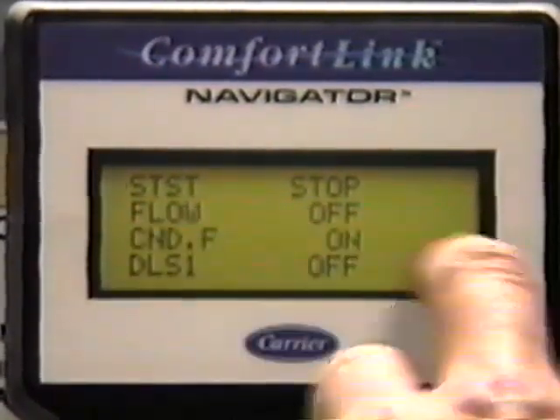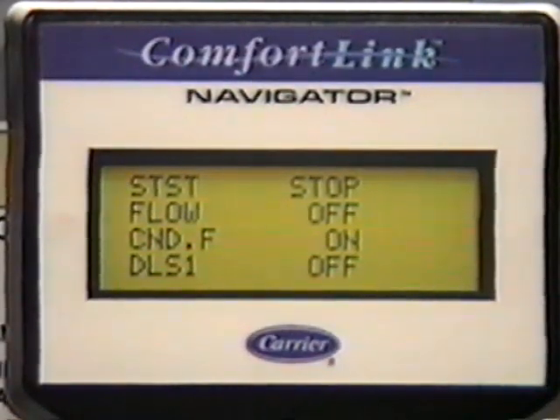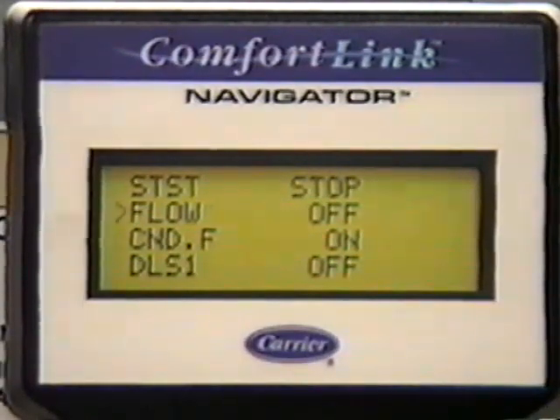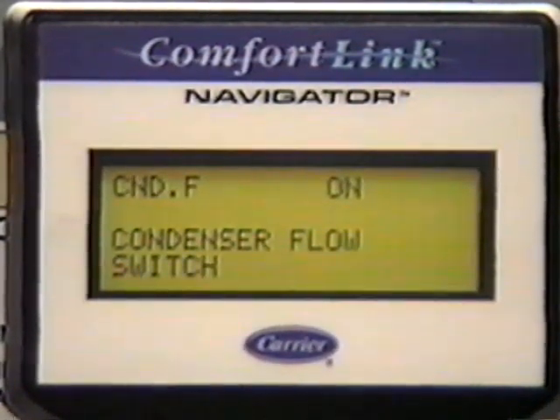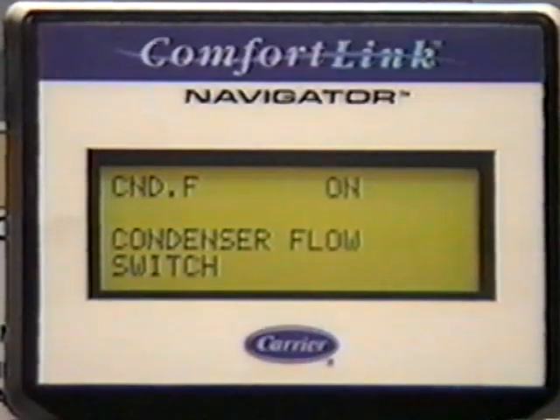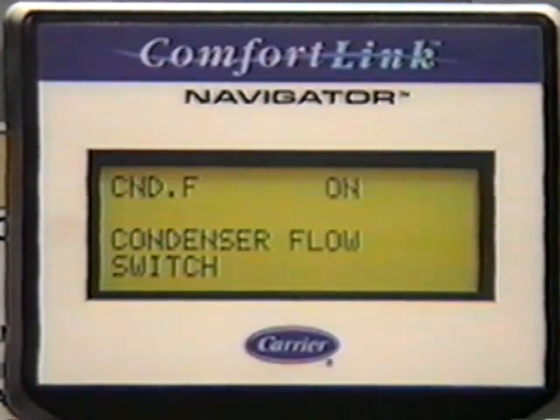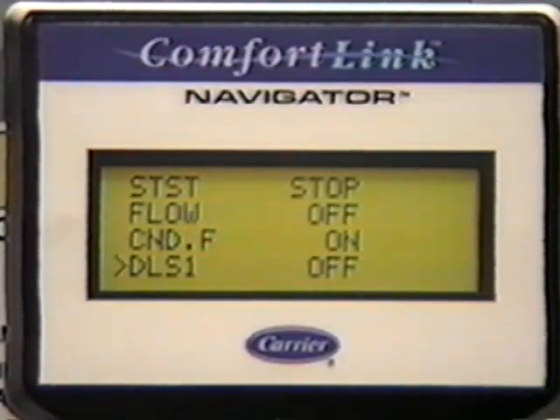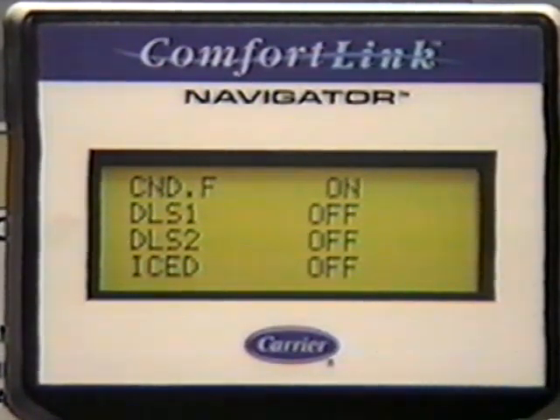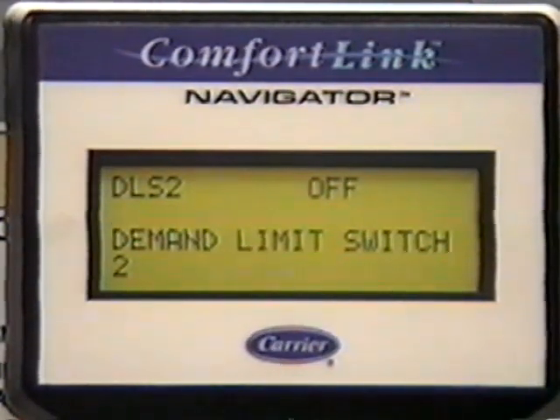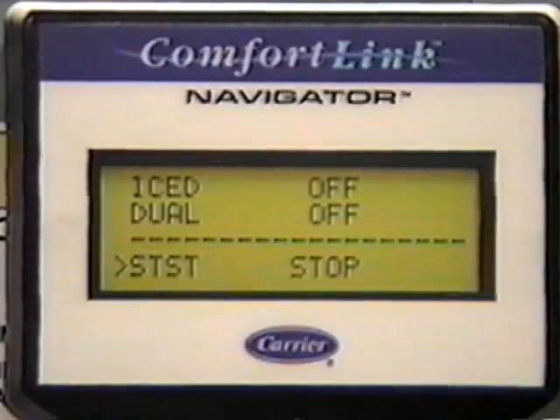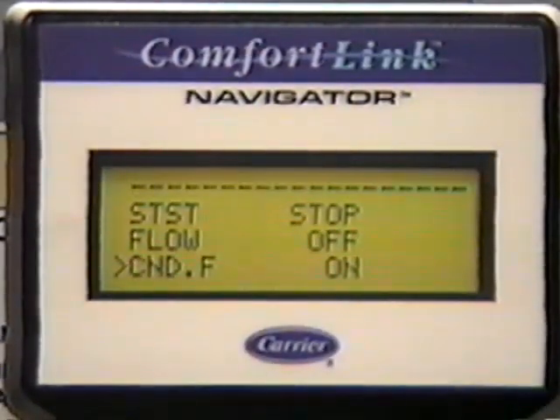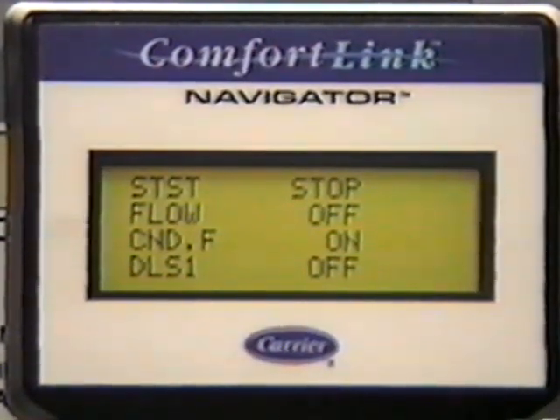So here we see our start-stop switch. The status of that is stop. Flow switch, it says it's off. Condenser flow switch, we're not utilizing. I don't believe there's one installed now. So when we did the initial configuration, we programmed out of there, so it's not even looking for that. Demand limit switches, again, those aren't being utilized. So a lot of these inputs, the general inputs, aren't being utilized. Primarily your flow switch and your start-stop switch.